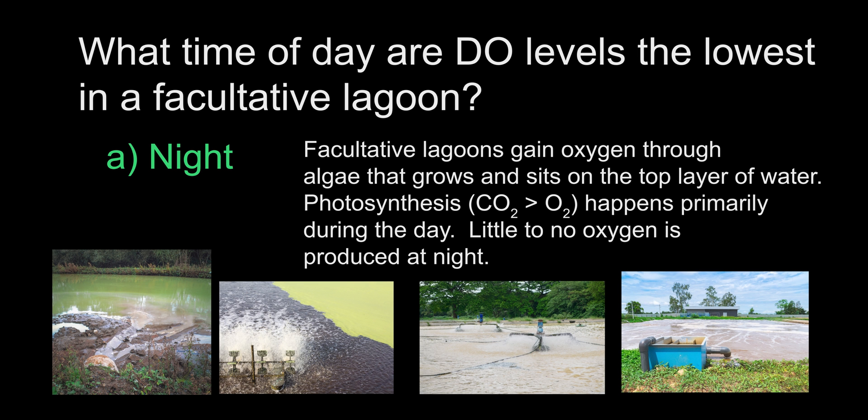The answer is A, night. Facultative lagoons are a simple and effective way to treat wastewater when permits are not very stringent. A traditional facultative lagoon will let mother nature do its thing. Photosynthesizing algae that grows on the surface of the lagoon will introduce oxygen into the water during the day, and then at night, when there is no sun, there is little to no oxygen production taking place. These types of lagoons are pictured on the bottom left. They may also be assisted with simple mechanical aeration techniques. Pictured on the middle right is a lagoon that is more similar to an aeration basin using heavy duty mechanical mixers, and on the far right is a lagoon using small bubble diffusers.